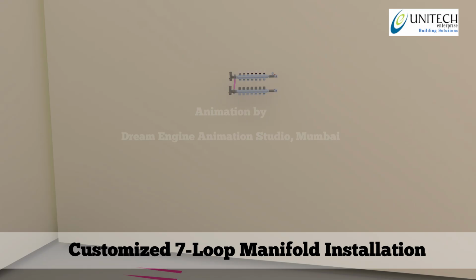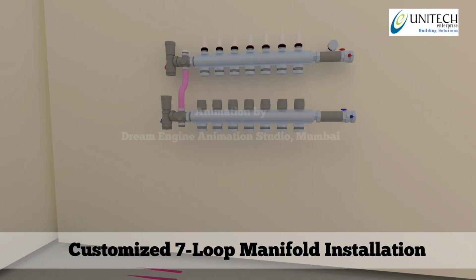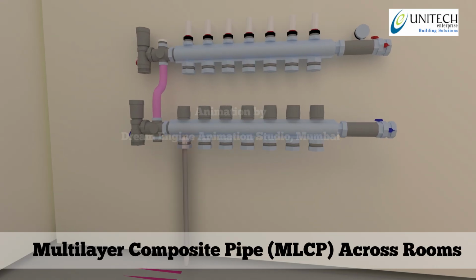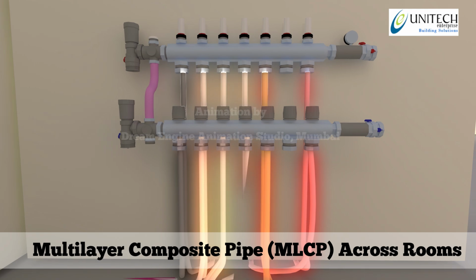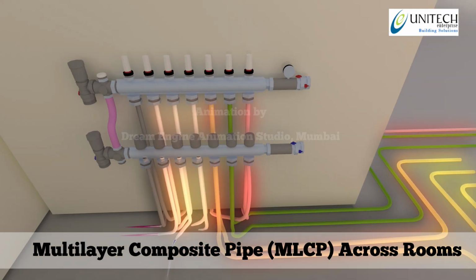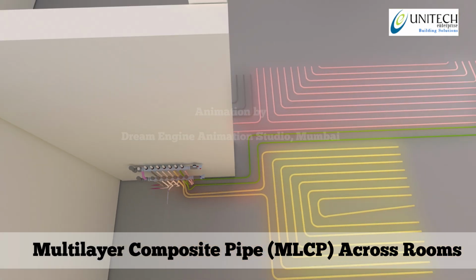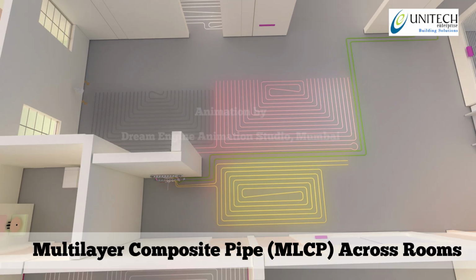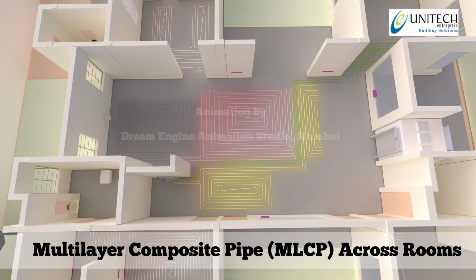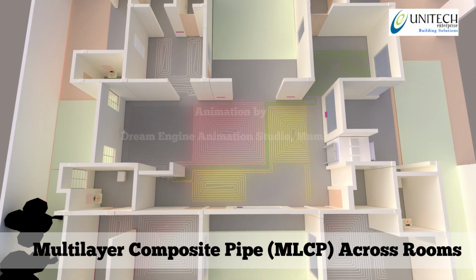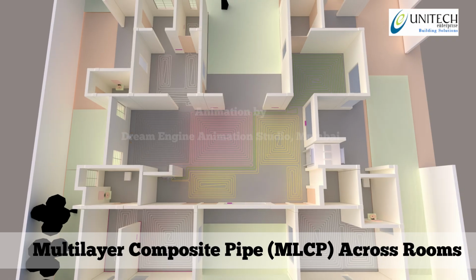A customized 7-loop manifold is then positioned. Multi-layer composite pipes, commonly known as MLCP pipes, are introduced and connected to the manifold. The MLCP piping network is carefully routed throughout each room, ensuring uniform temperature distribution across the entire floor area.